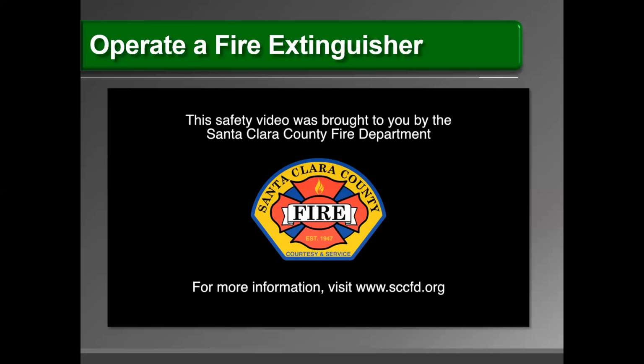And the acronym again was PASS. So it's pull the pin, aim, squeeze, whatever type of trigger you have. That's why you want to look at your fire extinguisher, and then sweep. And you want to go at the base of the fire. Like I talked about with the candle and the wick, right at the base of where the flame is on the wick, that's what you want to do when you're fighting the fire. So if it's a trash can, aim at the base, not the top of the flames, but at the base. Next slide.